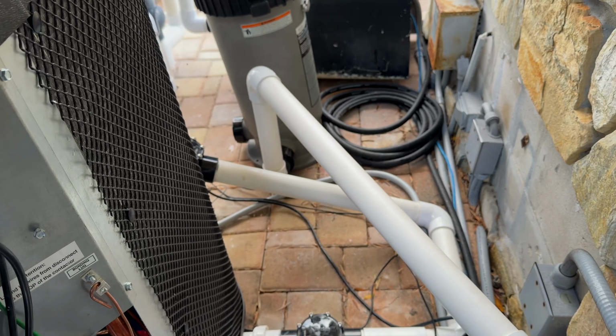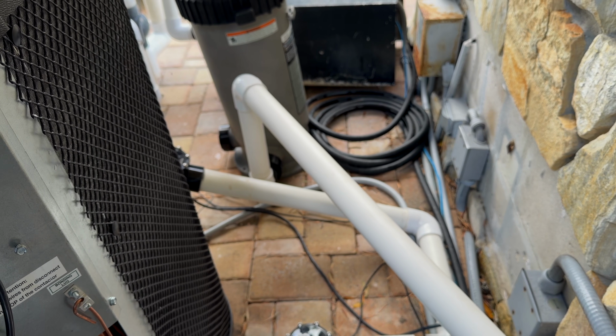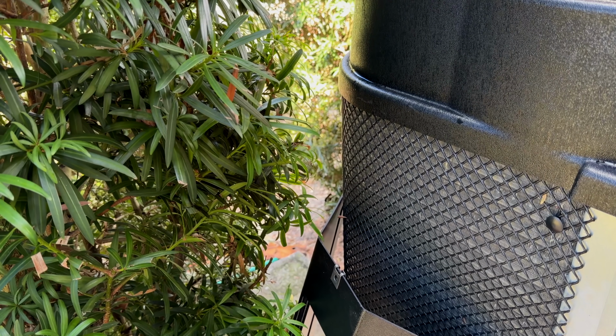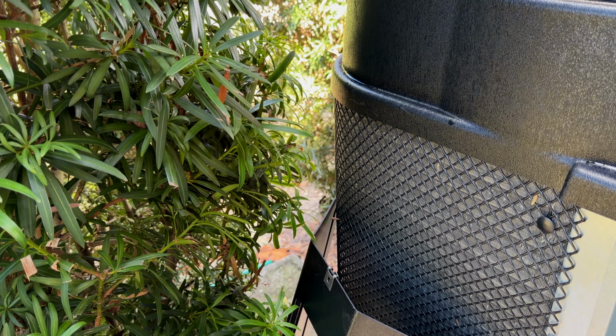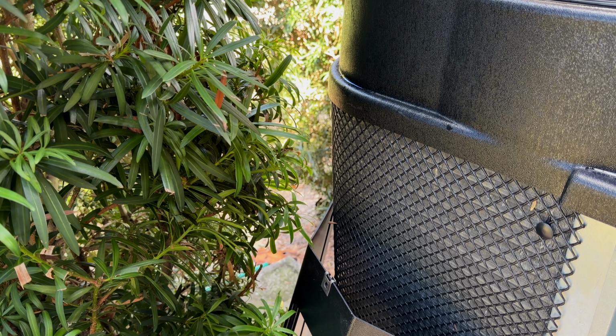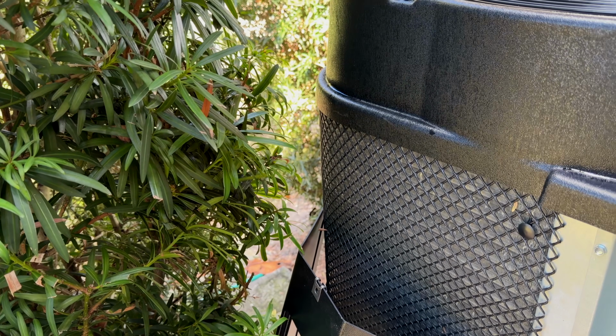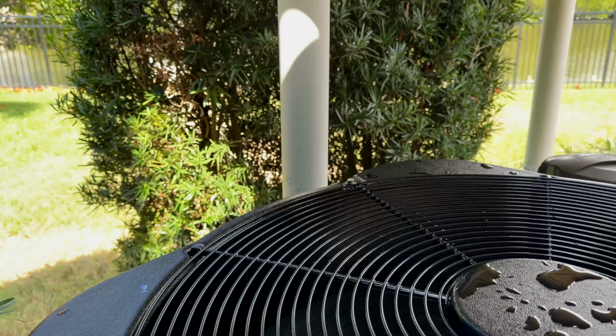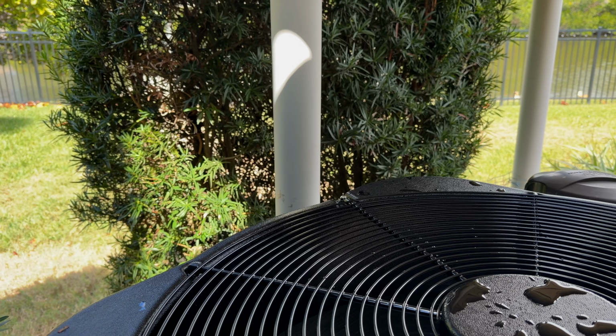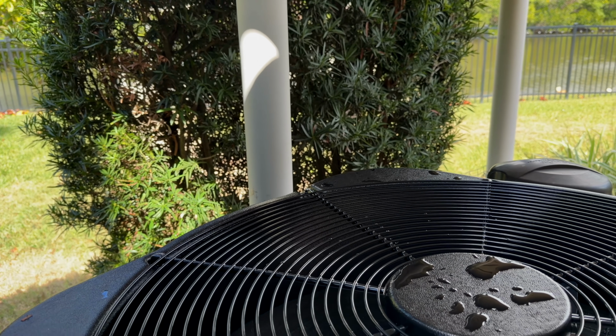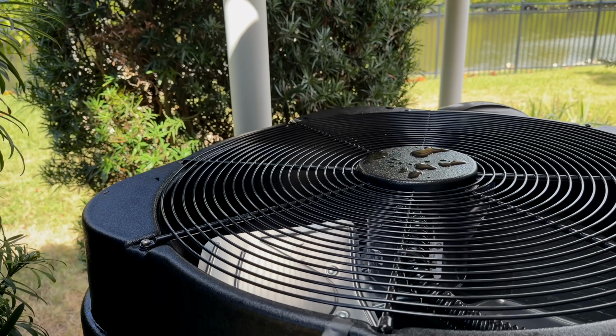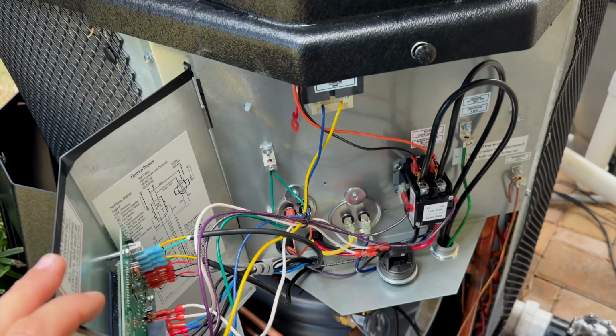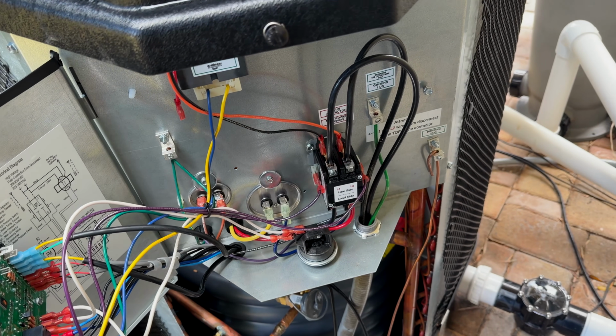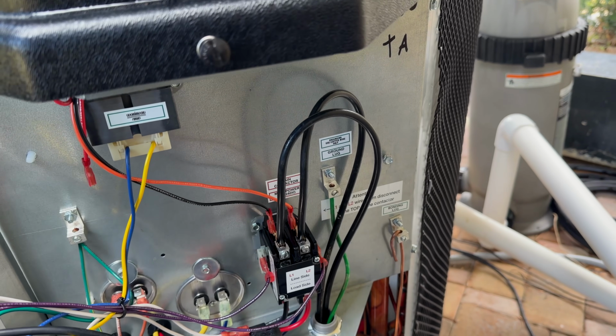I couldn't put the electrical over there because the plumbing impedes that 36 inches of workspace. Not to mention here, I probably couldn't get the thing installed and get the door open, much less this bush here impedes that 36 inches of workspace. Over here, that column, that bush, and what you guys can't see, pool equipment's over there - I couldn't put it over there because that impedes that 36 inches. So in other words, just make sure if you guys are installing these things, you're given enough space. So with that said, let's get into the electrical.